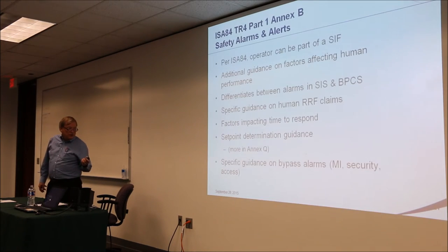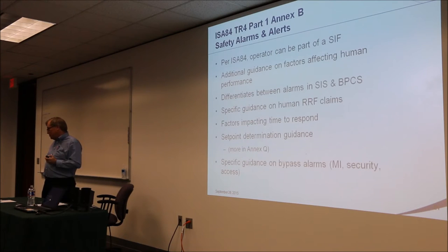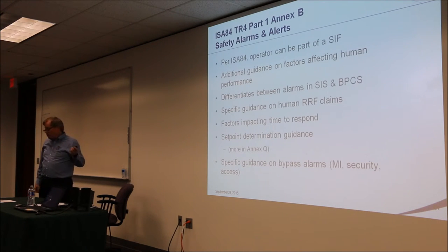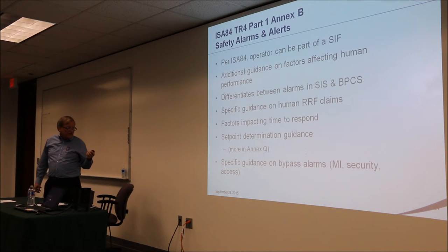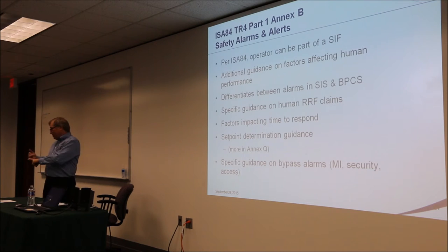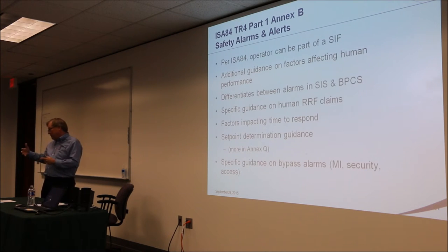TR4-04 is a long document — over 200 pages — consisting mostly of a series of annexes aimed at different topics within the ISA 84 umbrella. A few of those annexes are pertinent to safety alarms. Annex B is dedicated specifically to safety alerts and alarms, and there's a lot of good information there. It gives additional guidance on human factors, including a chart with specific guidance on risk reduction claims and other considerations. Set point determination is very important: you need to consider operating range, measurement uncertainty, and time available to respond, and the alarm set point must be coordinated with the corresponding SIF.